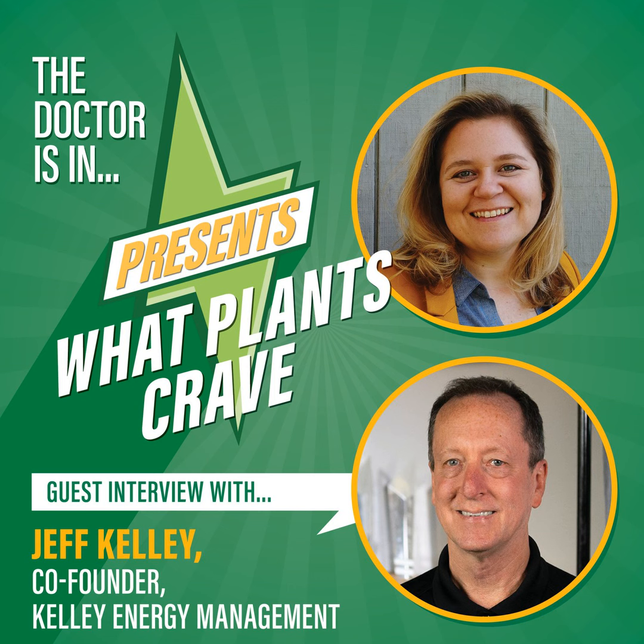I did do that on a facility in Michigan, and my curves were right there. Basically a flower room is night, day, lights out, and then you got a flat thing, and it runs kind of the same every month. So if you're looking for that pattern, that jump, and seeing how much of it was lighting, you can back that out. That's a simple thing, watts of lighting that's on. And then you can go in and say, well, the rest of that must be the fans and the air conditioners and the dehumidifiers running, that's what the utility is measuring.